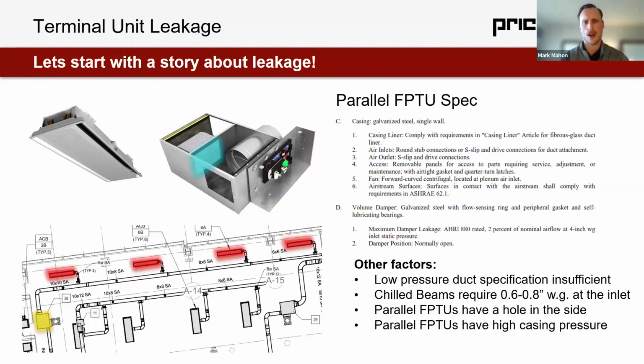For anyone who's not familiar with chilled beams, the short pitch is it's a sensible-only cooling solution that shoots high velocity air, creating a low pressure environment internal to the chilled beam that entrains and draws room air back up through a cooling coil that sensibly cools that air down and then shoots it to the space through nozzles. So this is a very energy efficient solution. It works great, but interestingly, it needs a lot of pressure at the actual chilled beam terminal to operate correctly. It needs 0.6 to 0.8 inches of pressure at the inlet.